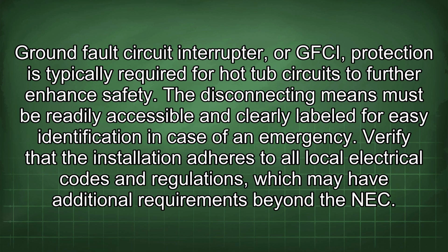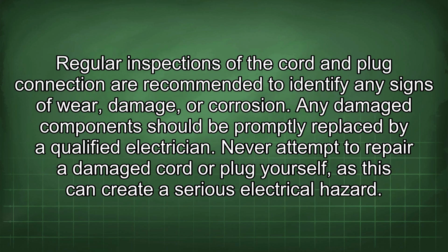Verify that the installation adheres to all local electrical codes and regulations, which may have additional requirements beyond the NEC. Regular inspections of the cord and plug connection are recommended to identify any signs of wear, damage, or corrosion. Any damaged component should be promptly replaced by a qualified electrician. Never attempt to repair a damaged cord or plug yourself, as this can create a serious electrical hazard.